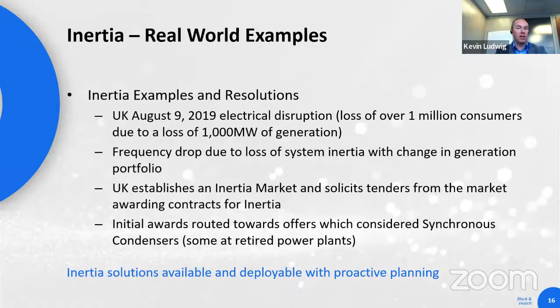All the generation assets connected into the power system have under-frequency protection. If the frequency drops below a certain level instantaneously, the generation is removed from the system to protect it, because generation can't run at this lower frequency - it can damage the generation assets. Then you get a situation with cascading loss of load and generation. In this event, over a million consumers were disconnected and didn't have power. So that lightning strike caused the loss of power for a million consumers.